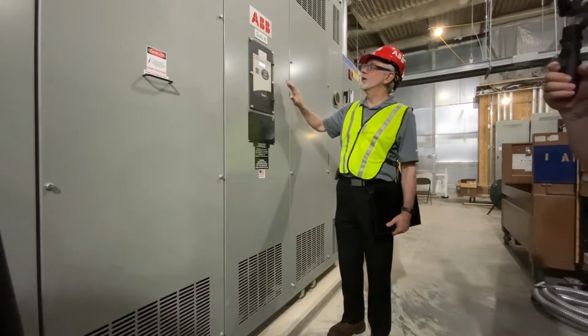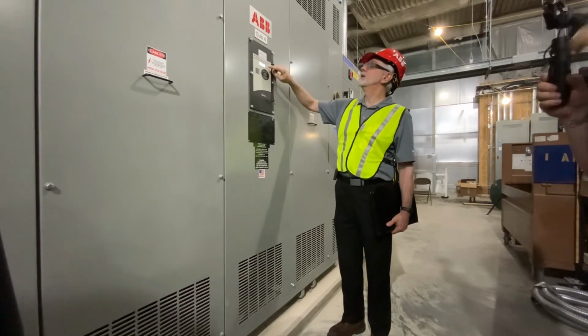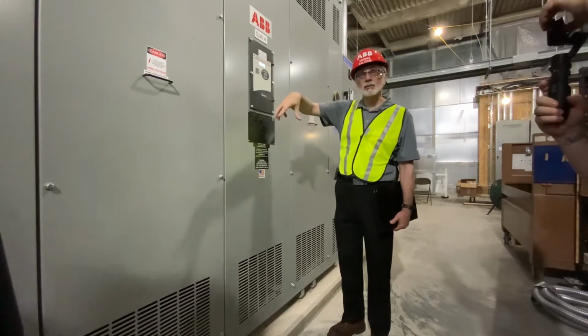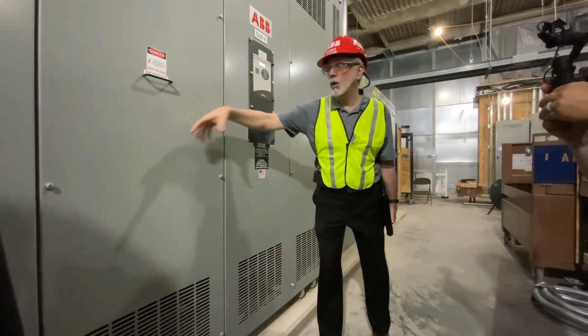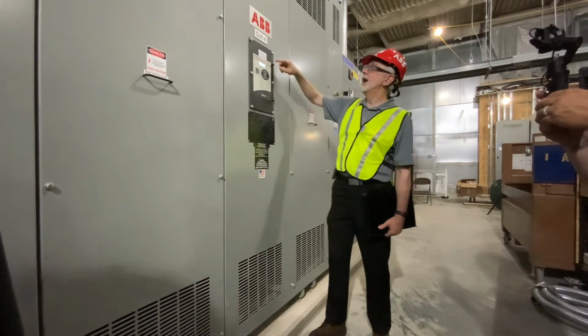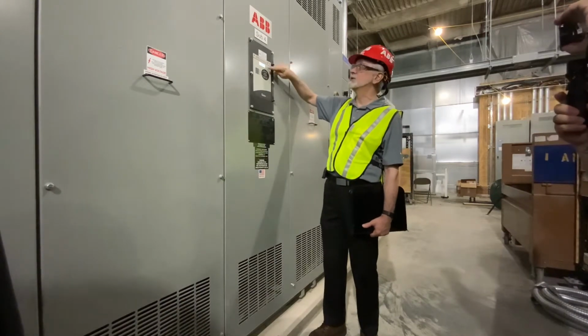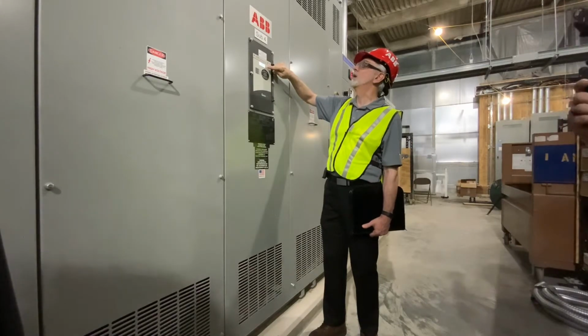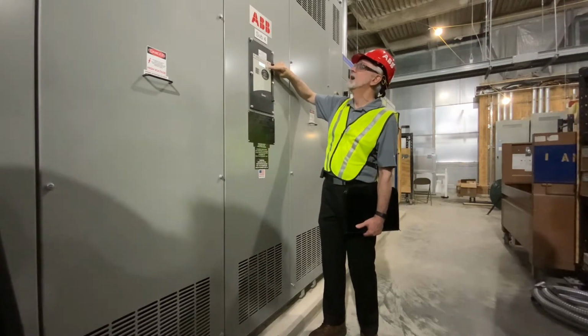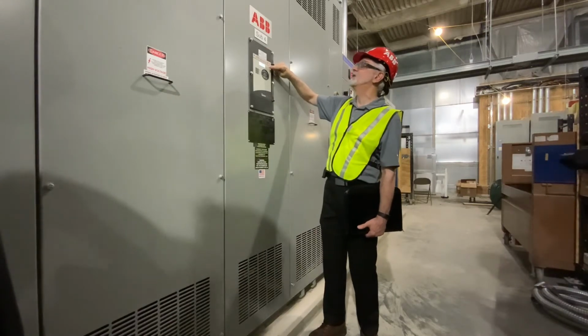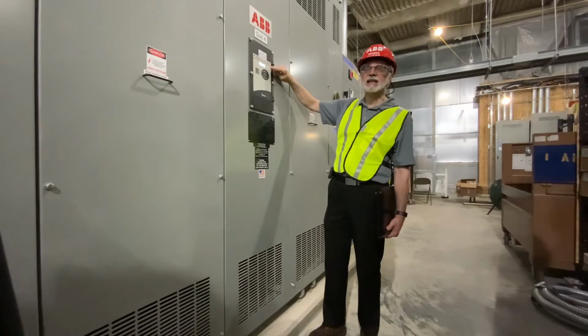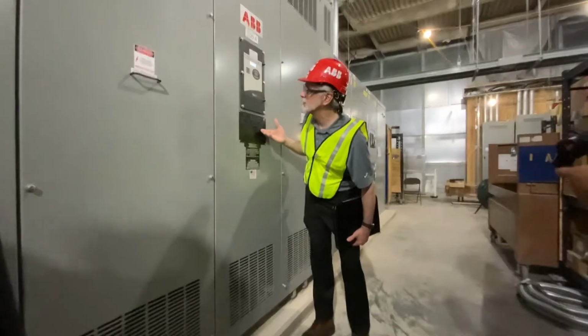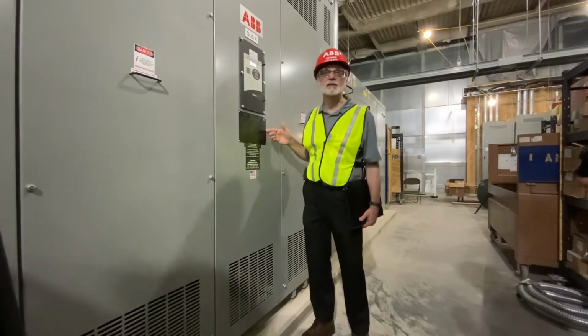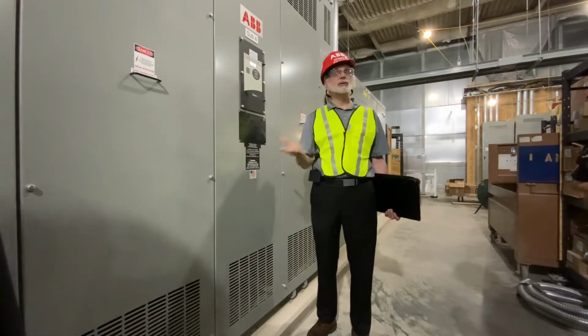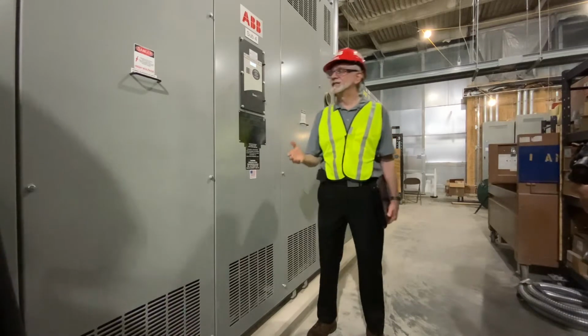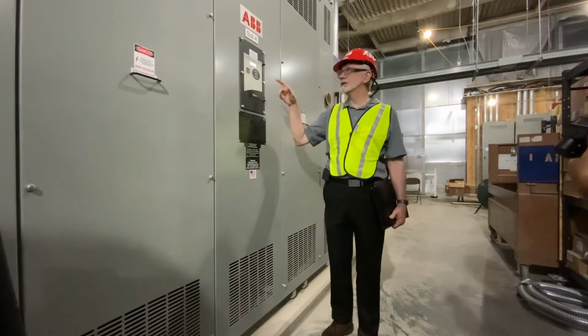This is your transformer temperature monitor. You'll notice that it has thermocouples on the A coil, the B coil, and the C coil, and it automatically steps through and tells you what the temperature is on each coil. So for example, here the left one is 50 degrees C, the center is 52, and the right is 53, and it's a max of 68. Well, this particular unit is rated up to 150 degrees C. So your transformer is running pretty cool. Even at its peak, it was only at 68.